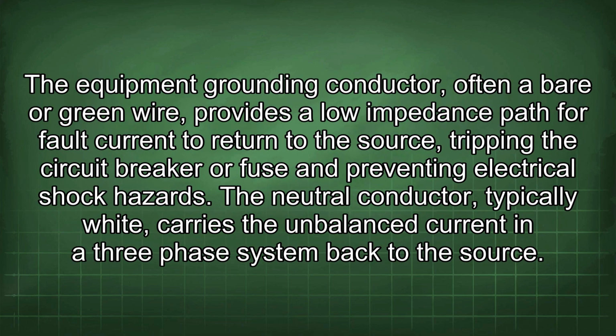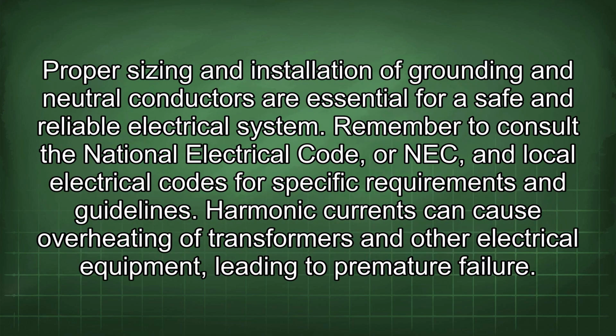Ensuring proper grounding is crucial for safety and minimizing electrical noise. The equipment grounding conductor, often a bare or green wire, provides a low impedance path for fault current to return to the source, tripping the circuit breaker or fuse and preventing electrical shock hazards. The neutral conductor, typically white, carries the unbalanced current in a 3-phase system back to the source. Proper sizing and installation of grounding and neutral conductors are essential for a safe and reliable electrical system. Remember to consult the National Electrical Code, or NEC, and local electrical codes for specific requirements and guidelines.